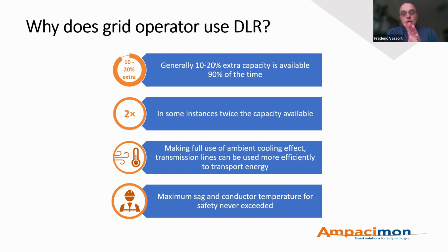And what we note, and I'm just trying to mention some orders of magnitude here, is that whenever lines are equipped with dynamic line rating, the capacity gains typically range in 10 to 20%, available 90% of the time. Of course, there are also some instances where the capacity can be much higher. We quite often see capacity doubling when the wind blows and when the weather is cold, but that's not really the point. The point is to make sure that that capacity is available most of the time, to be able to forecast it and to be able to make sure that under no circumstance do we put the grid at risk, which is why monitoring is important.